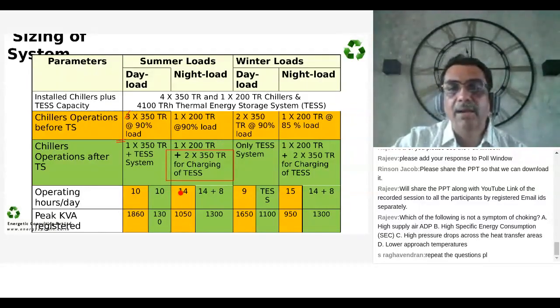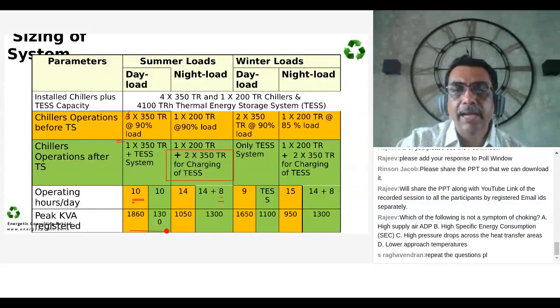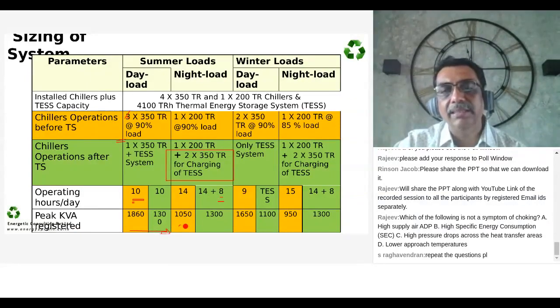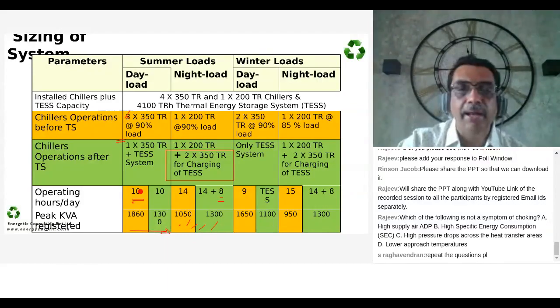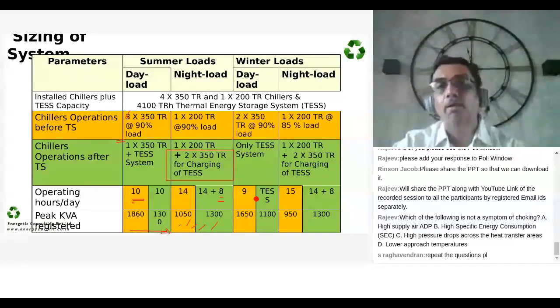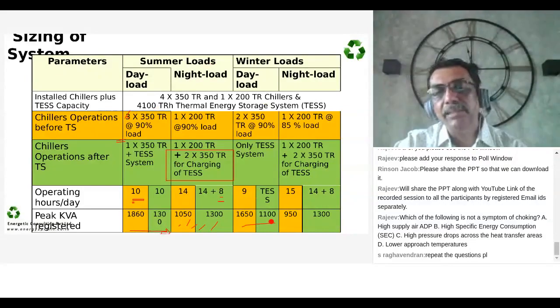These are the operating hours per day before and after. Green is after. 10 hours, no change. Plus 8 hours is the thermal storage operation. You can see the peak demand registered has reduced from 1860 to 1300 during the daytime. Now at night time there is an increase in demand, but this is not recorded. There is no billing for that. So there was about 560 kVA of demand reduction equivalent of benefit in summer, very similar in winter.